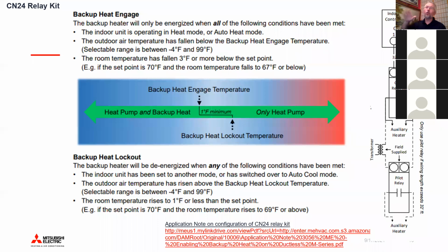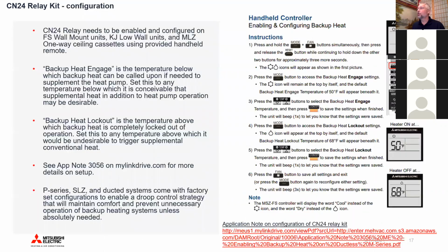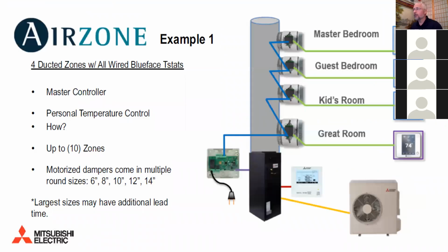So you might say, there's no way on earth that I want my backup heat source to come on when it's above 50 degrees Fahrenheit or 40 degrees, whatever set point. It doesn't really matter at that point, but whatever temperature you say, I definitely only want to rely on my heat pump above this temperature. There's absolutely no reason that a boiler would ever come on at that temperature. That would be your lockout temperature. And then your backup heat engaged temperature would be some temperature below that. The heat pump's going to continue to operate through the entire range. It's only going to call for the backup heat below that temperature when there's absolutely a need and you're exceeding your droop. Okay, so that's the CN24 solution, and turning it on.